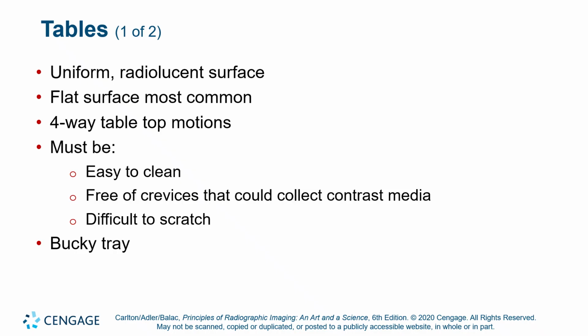Four-way tabletop motions. Yes, you should have a free float type design such that you click it like a toggle switch, and it allows you to move the surface of the table up and down, left to right, back and forward, and so on. Now, the up and down motion is not part of the four-way floating tabletop. That's usually a motor in the telescoping base that is raising and lowering a piston or a rack and pinion gear drive.